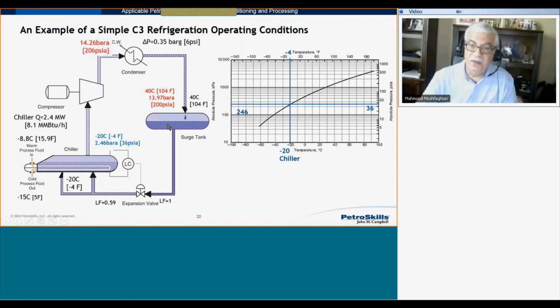Fahrenheit. We know the condensing temperature of the condenser. So let's identify that, 40 degrees C or 104, and then we can read the vapor pressure of propane, 200 psi on the right-hand side, and the left-hand side 1400 kilopascal.